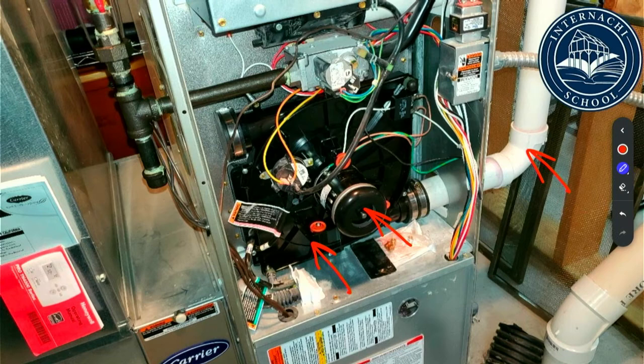I mean, it's going to be really quick. And I can't put plastic on the other ones because I'm going to have 300 to 500 degrees of heat coming out of there, and that's actually going to melt those pipes. So, if this is plastic, then the pipe has to be plastic. And then if we look, we'll see our pressure differential switch there. We're going to have our burner chamber up here. The single wire coming off of there, that's my flame sensor. And then I should have an igniter in here over on the right.